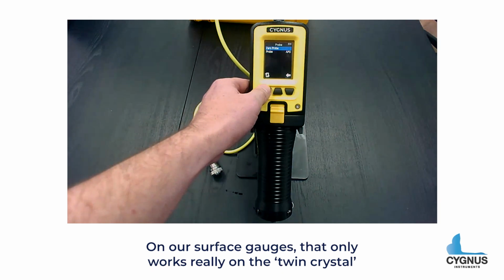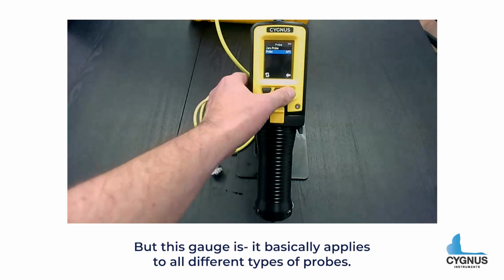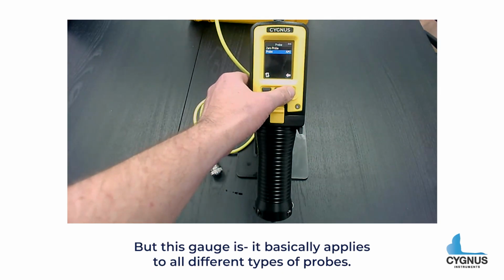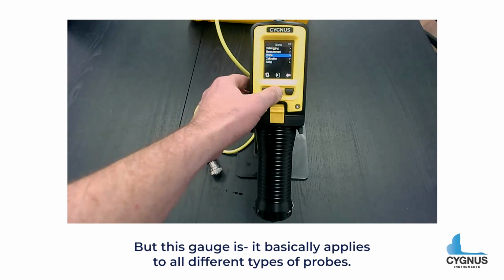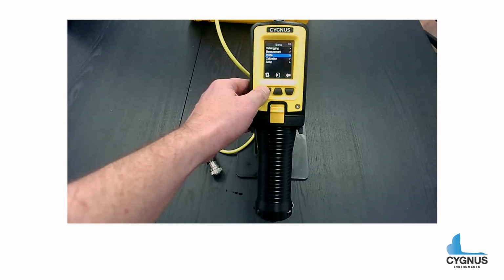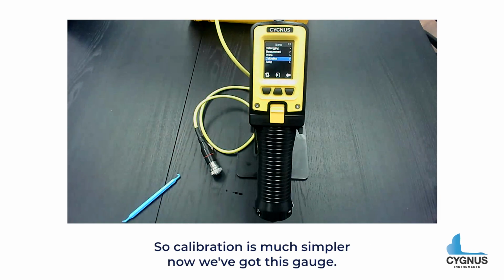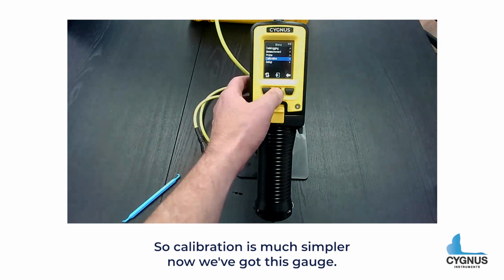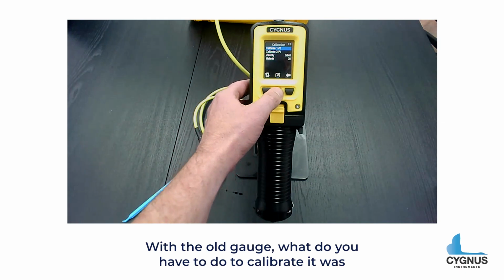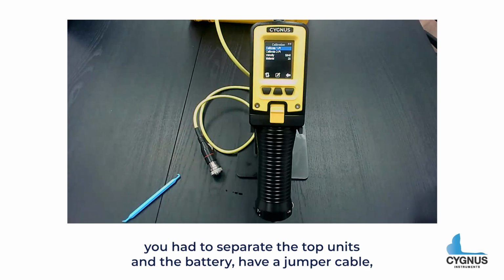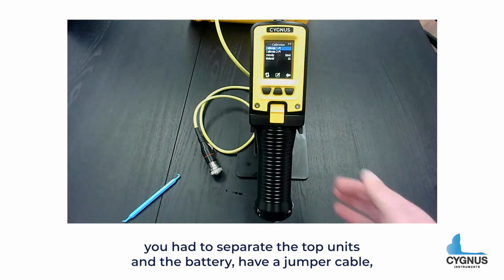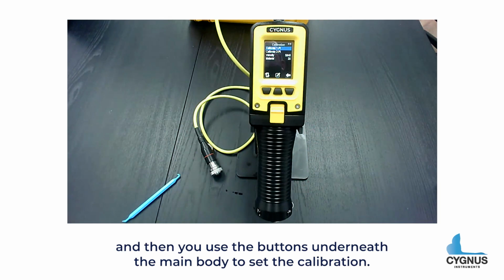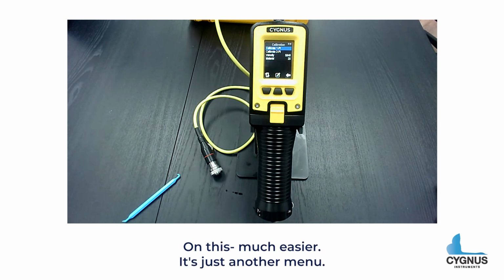Surface gauges only work really on the twin crystal, but this gauge basically applies to all different types of probes. So calibration is much simpler now. With the old gauge, what you had to do to calibrate was separate the top unit and the battery, have a jumper cable, and then use the buttons underneath the main body to set the calibration. On this, much easier.